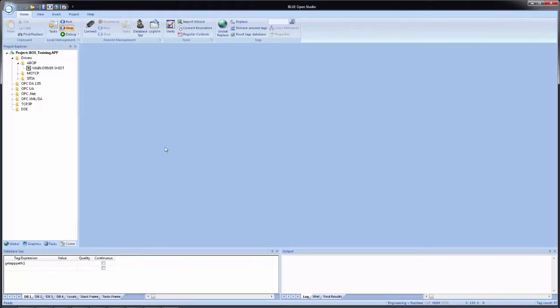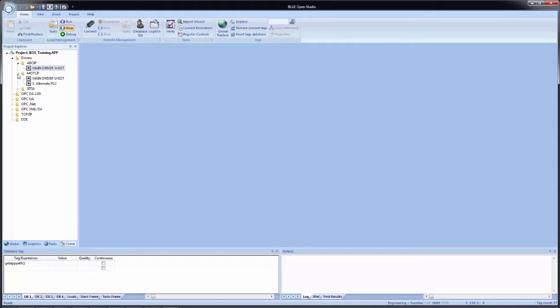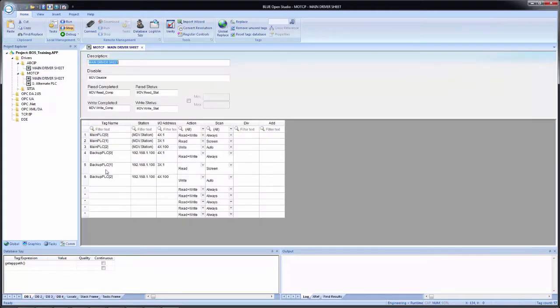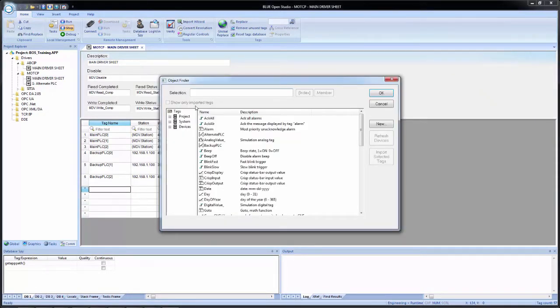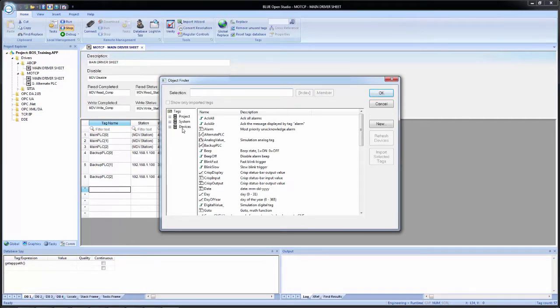Now, if we wanted to add one of the newly integrated tags to our application. Let's say, for example, we wanted our application to act as a bridge between the Allen Bradley and the Modbus device. If I come into the main driver sheet for MOTCP, let's say I wanted to add a new tag here. Click on insert tag. We now see in the object finder under the tags list on the left hand side, a new item called devices.